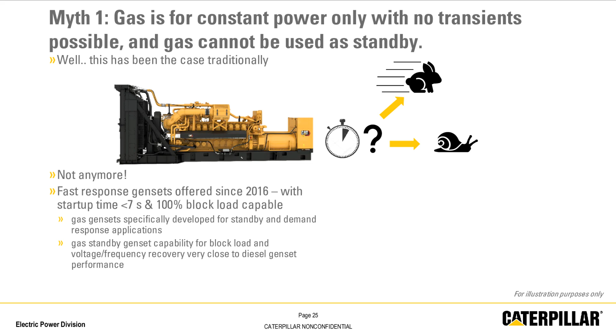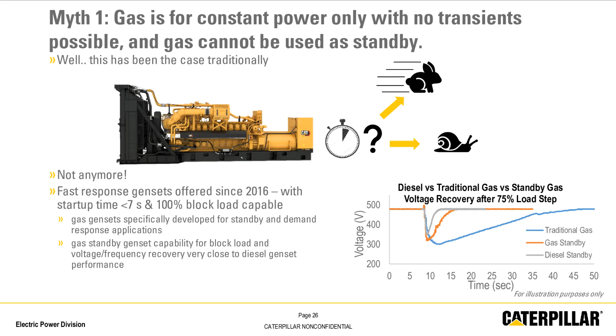Well, you probably have guessed it already: this perception is outdated. Optimization for purely stationary operation has traditionally been the case, but this has changed. For many years now, gas gensets in the most important power ranges are available that can even be used for full standby applications like diesel gensets, starting up in less than 7 seconds for full NFPA 110 Type 10 applications, and able to take 100% block load at once with performance that can keep up almost to standby diesel genset levels, as shown in this illustration on the right. So I would say this myth is busted.